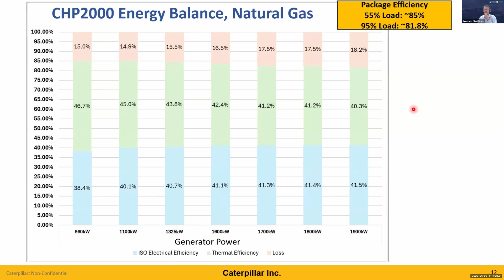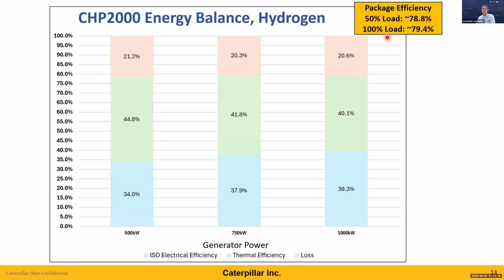And here is a plot for the 100% hydrogen operation. Again, ISO electrical efficiency, thermal efficiency, and the losses from the system. In this case, at 50% load, the overall package efficiency was about 78.8%, and with 100% load, it was 79.4%.